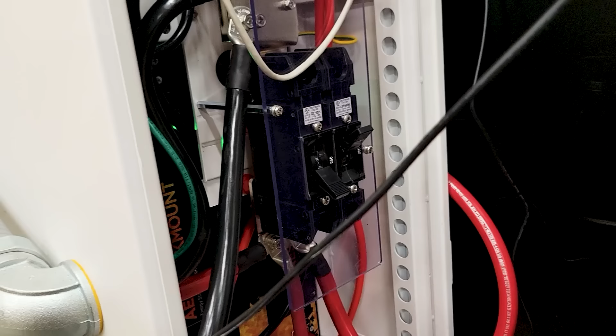Okay, so this one just tripped. At 6 minutes, the breaker on the right tripped. We had the same load as before, and it tripped at 6 minutes. The testing on this cabinet did not go as planned. I was hoping we could pull the full 500 amps from it, but as you can see, there are slight manufacturing differences in the circuit breakers. So one circuit breaker was tripping a little bit before its 250 amp rating, so too many amps were flowing through the other one. So this is something to keep in mind if you're going to do parallel circuit breakers, that you might have to derate the overall capacity.